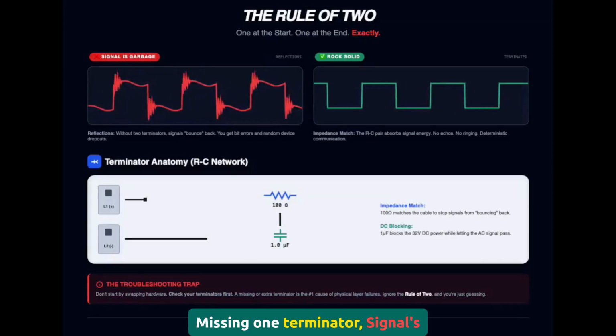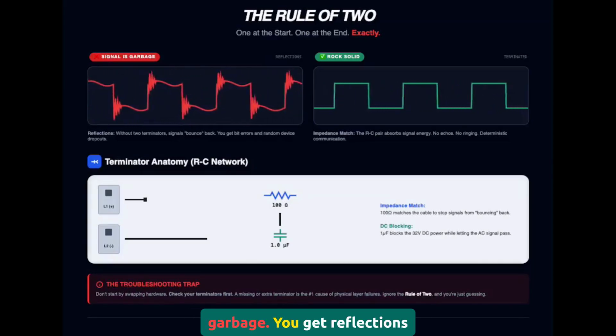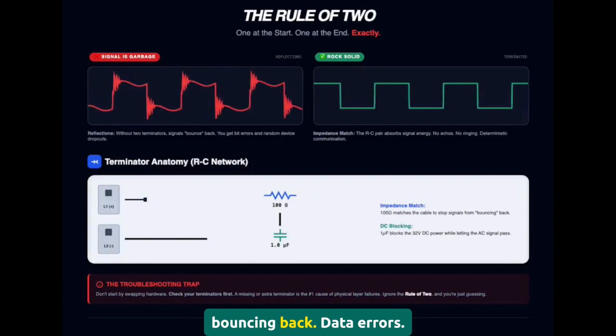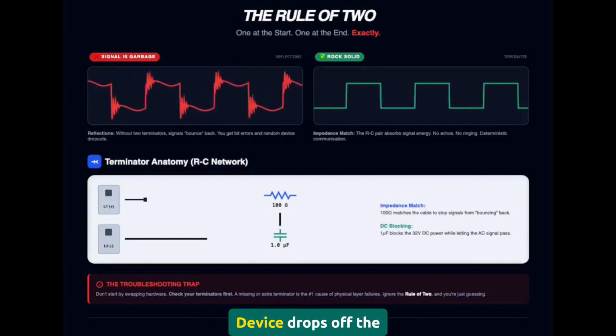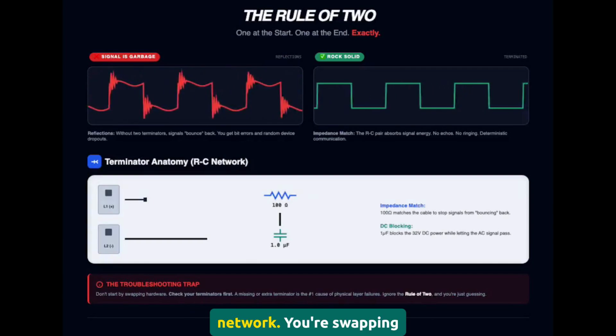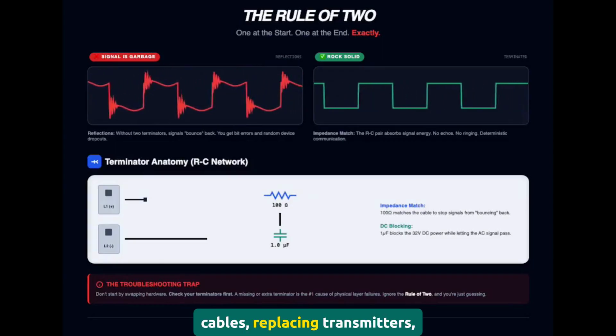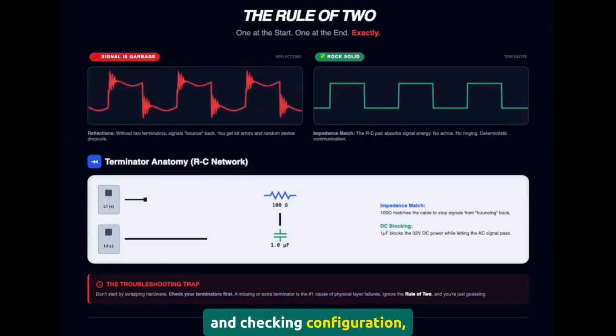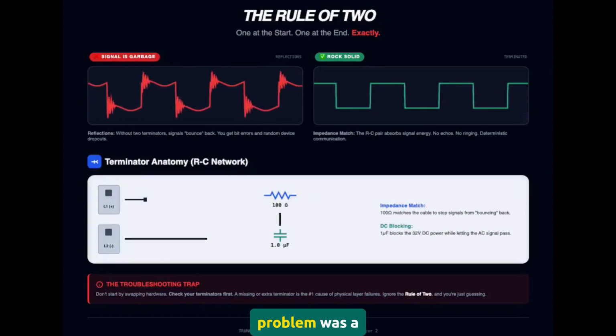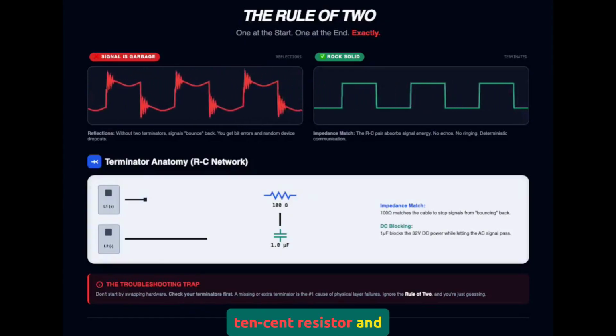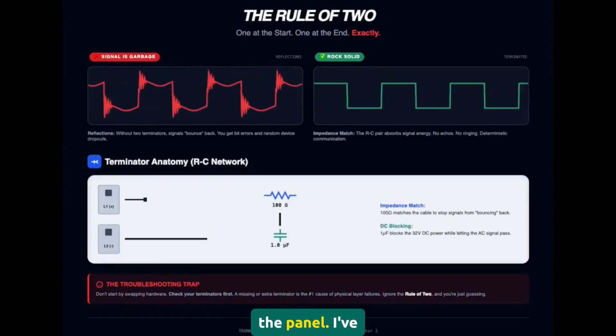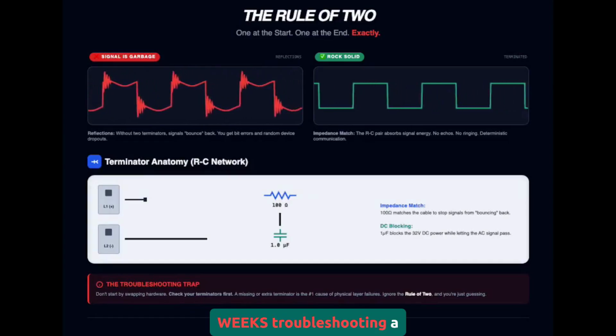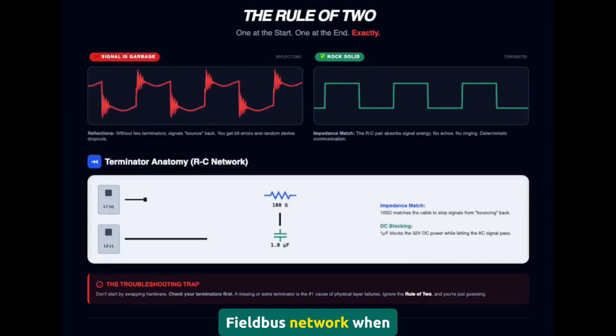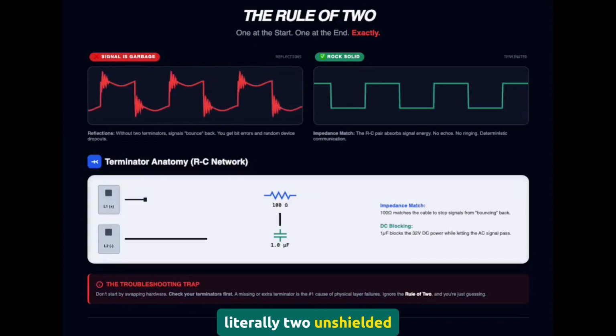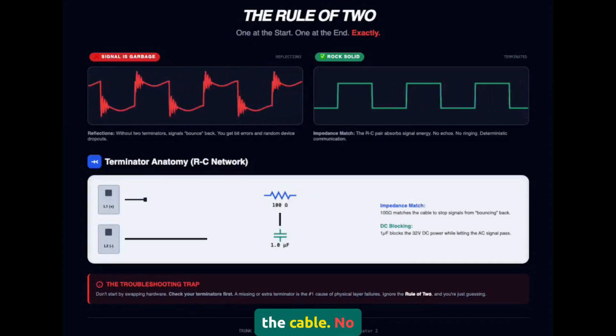Missing 1 terminator, signal's garbage. You get reflections bouncing back, data errors, device drops off the network. You're swapping cables, replacing transmitters, and checking configuration, all when the problem was a 10-cent resistor and a capacitor at the panel. I've seen techs spend weeks troubleshooting a Fieldbus network when the issue was literally 2 unshielded wires hanging at the end of the cable.